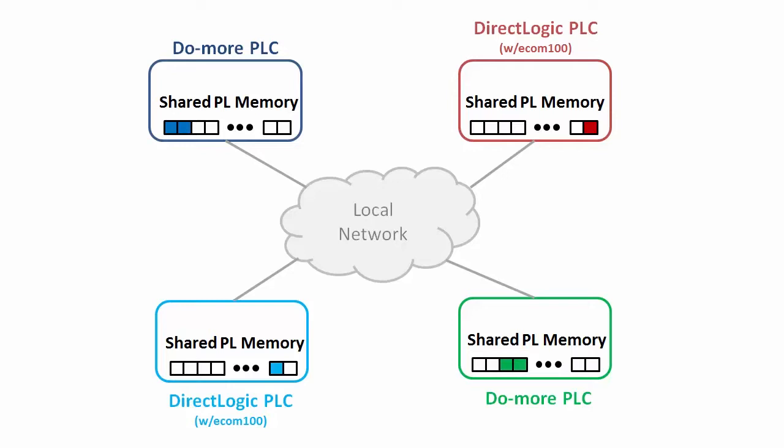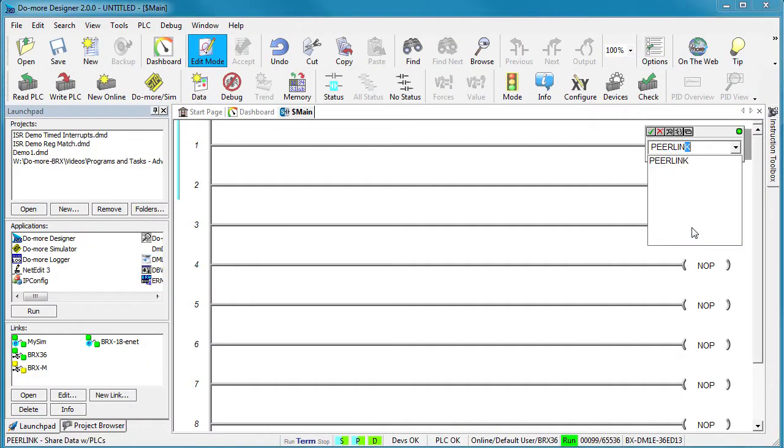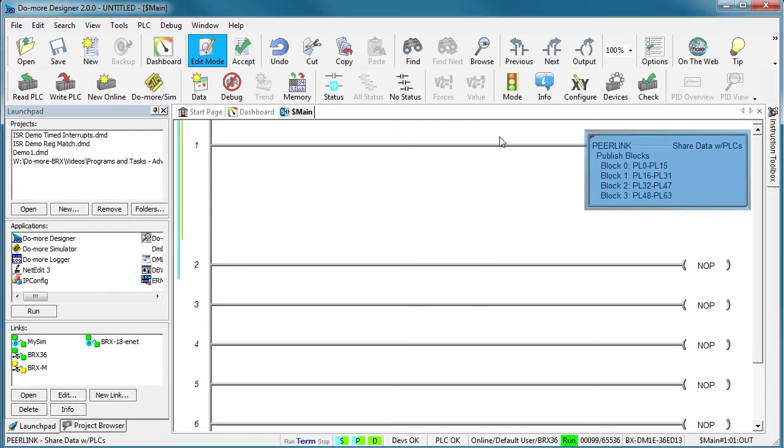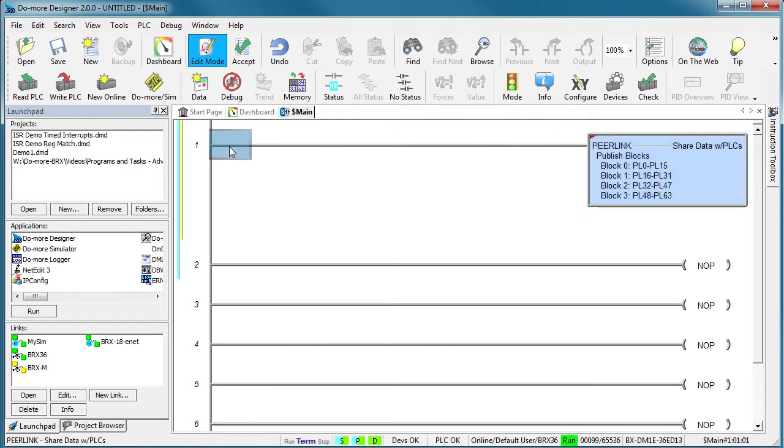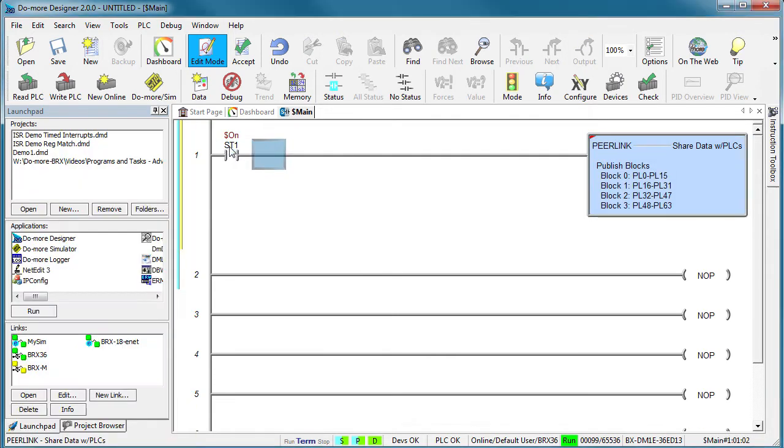And when the PLC writes to its portion of the Peerlink memory space, everyone can see it as if it's just another block of local memory. And it's so easy to use. You just drop a Peerlink instruction on a rung, select which blocks of the shared memory this PLC owns and you're done. Each Peerlink block has 16 memory locations so there's a total of 256 PL memory locations. This is an asynchronous instruction so as long as it's enabled it will update the Peerlink memory space.